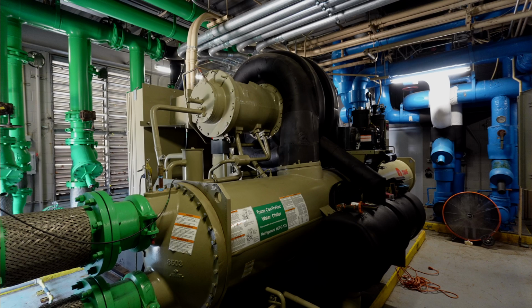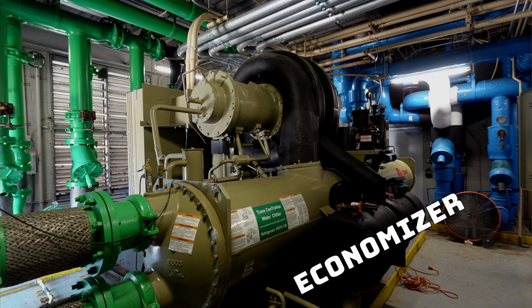But with a centrifugal, York has come out with their YKEP series, and then Trane with their CVHs. Those have flash tank economizers as well, and those just pull directly off of the top of the flash tank back into the suction side of the compressor. When you're looking at a CVH, you'll see the big black insulated cylinder on the side of the condenser barrel. That's your economizer assembly. So those are your chiller economizers.